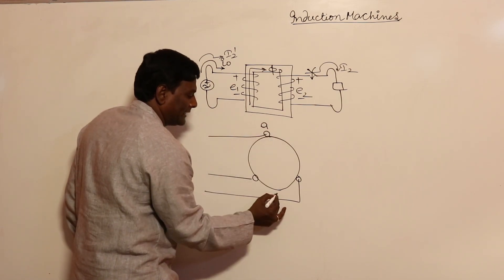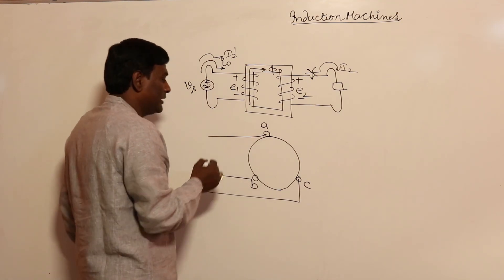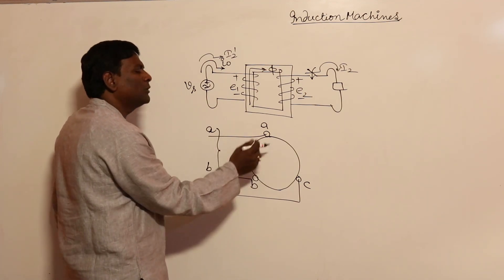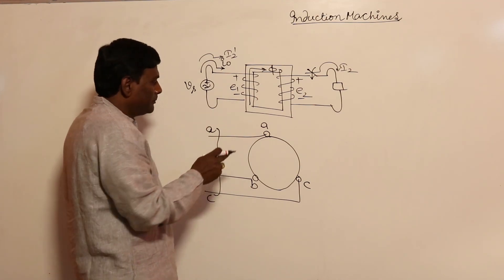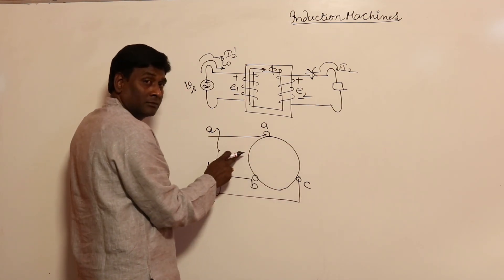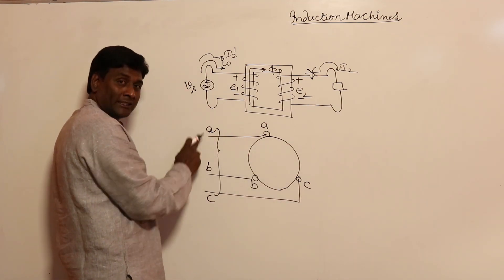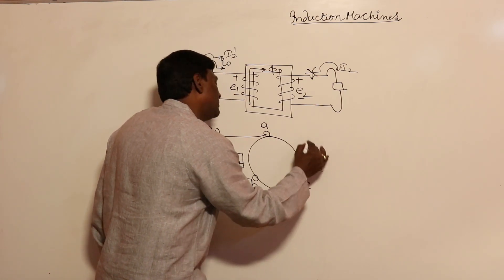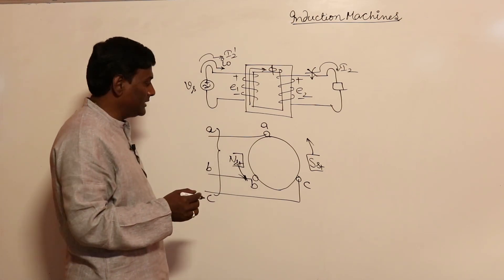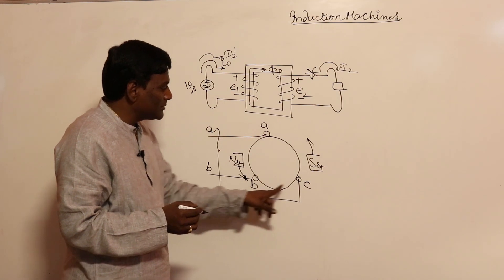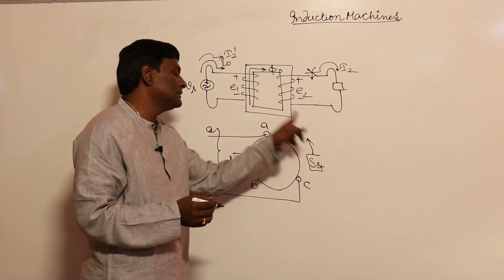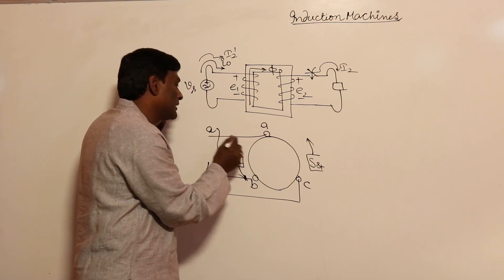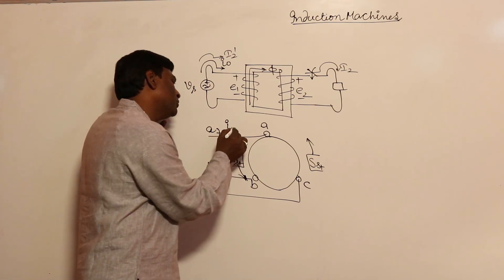In an induction machine, consider stator windings a-a', b-b', c-c'. If we supply three-phase voltage a-b-c here, the space-displaced windings connected to time-displaced voltages will automatically form a rotating magnetic field. This RMF rotates at synchronous speed in the direction of phase sequence A-B-C. Even with no rotor present, flux is being set up in the air gap by the stator no-load current.